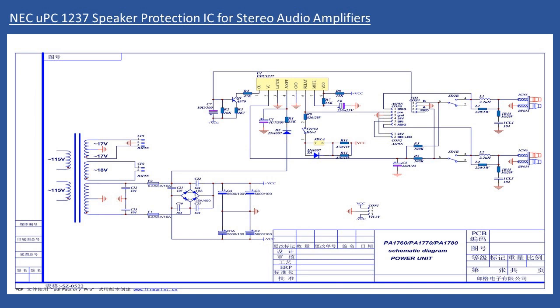Depending on circuit design, you can control the amount of gain, so you don't get a huge amount of amplification, which would be the case if you didn't have any sort of feedback connected for the operational amplifier. But with the op amp in this example, it's being used as a comparator, and what a comparator is doing is you have what we call VREF, or V reference. This is the reference point, and here they're monitoring the output across the speaker terminals, and that is the V actual. It should be a nominal value, ideally as low as possible, and that then goes to a multi-pin connector, and on the right-hand side I say status signals are read by the CPU.